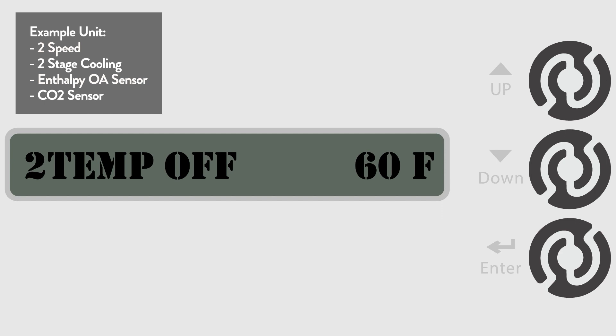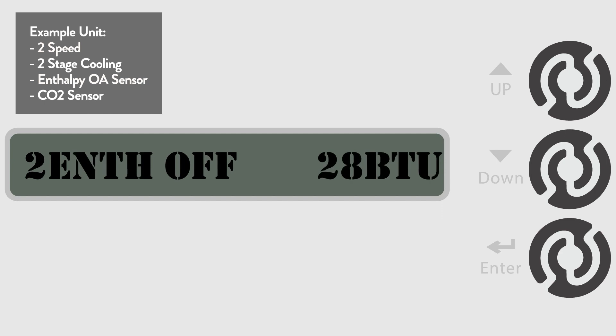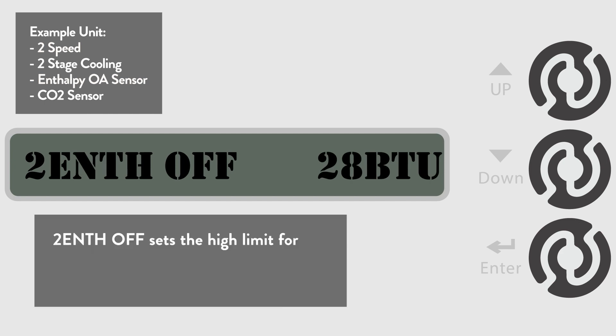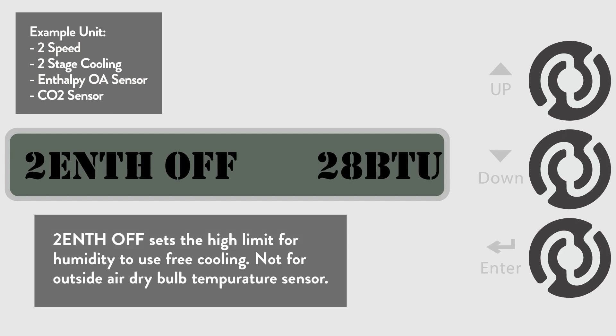Go to the 2ENTH OFF menu. This sets the outside air humidity limit where the economizer free cooling is locked out. The default is 28 BTU per pound, but we will change the setting to 25 BTU per pound.